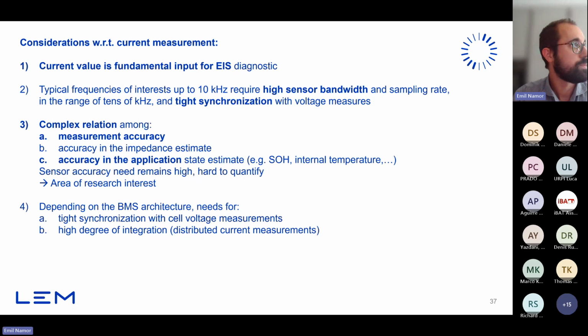In terms of what this requires from current sensors, it's primarily a bandwidth requirement, because impedance is typically measured up to 10 kilohertz, which requires quite high bandwidth in the battery current sensors. Previously, when state of charge was the only function using current measurement, a sampling rate of 10 or 100 milliseconds was enough. Now we're talking about microseconds for synchronization and sampling, which is definitely a challenging requirement we're working on.